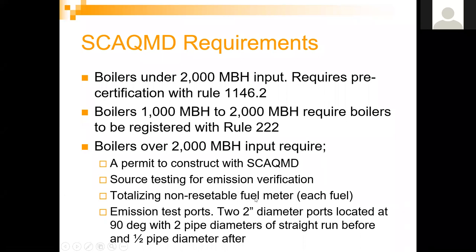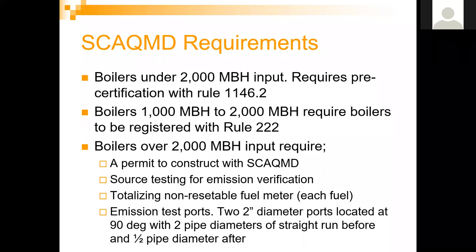You also need a totalizing non-resettable fuel meter. For gaseous fuels, South Coast AQMD requires these meters to be both pressure and temperature compensated, and non-resettable, so the air district can check how much fuel has been burned and calculate emissions at your facility. They also require emission test ports: two two-inch diameter ports located at 90 degrees along the circumference of the stack, with two pipe diameters straight run before and one-half pipe diameter straight run after, to ensure laminar flow during emission testing.